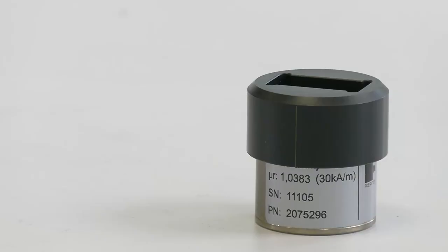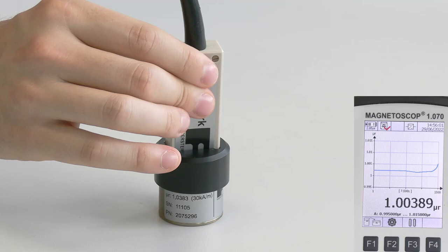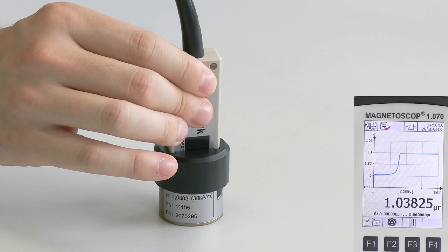Our standard value of 1.0383 is also related to 30 kiloamps per meter. Now we move the probe on our standard and we get the same value written on the standard, so our system is ready for a safe measurement.